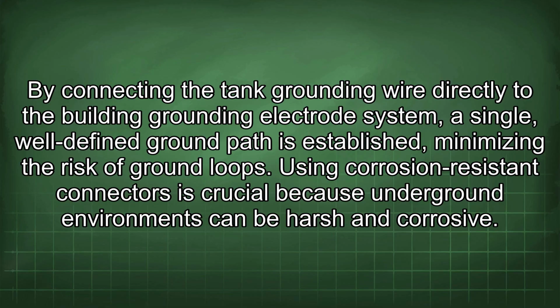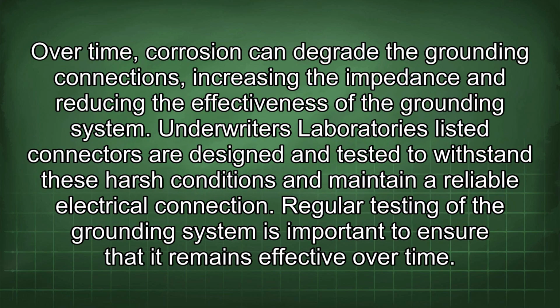Using corrosion-resistant connectors is crucial because underground environments can be harsh and corrosive. Over time, corrosion can degrade the grounding connections, increasing the impedance and reducing the effectiveness of the grounding system. Underwriters Laboratories listed connectors are designed and tested to withstand these harsh conditions and maintain a reliable electrical connection.